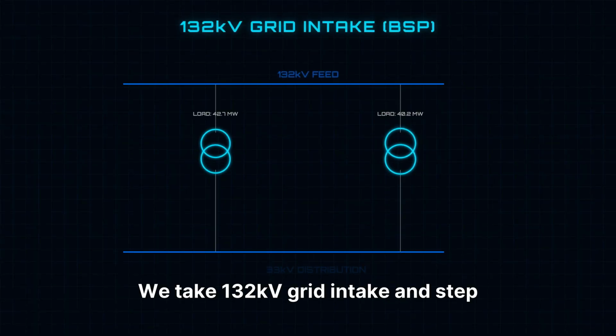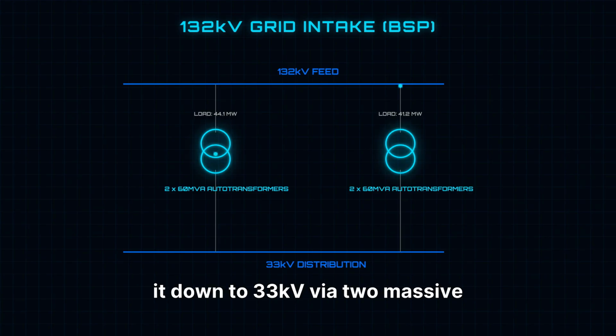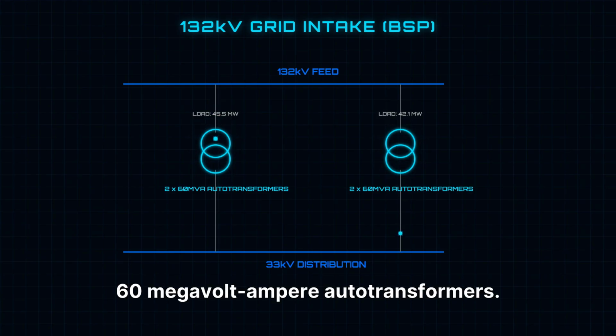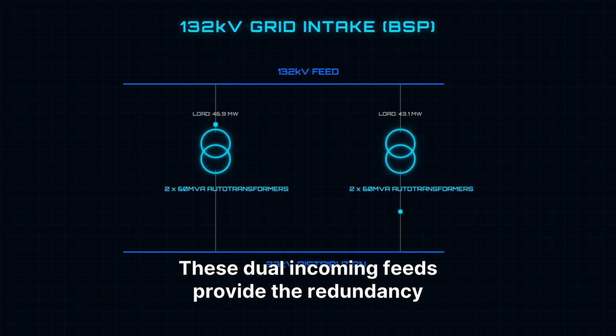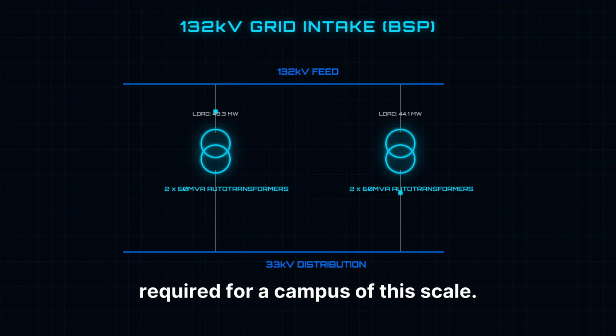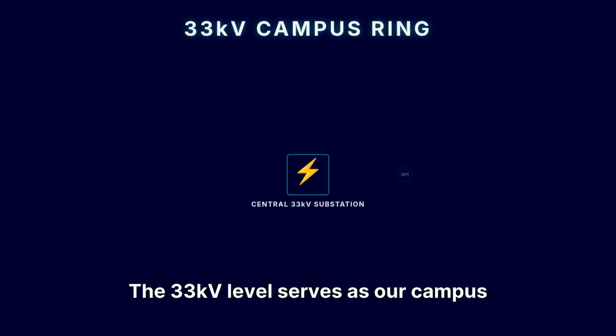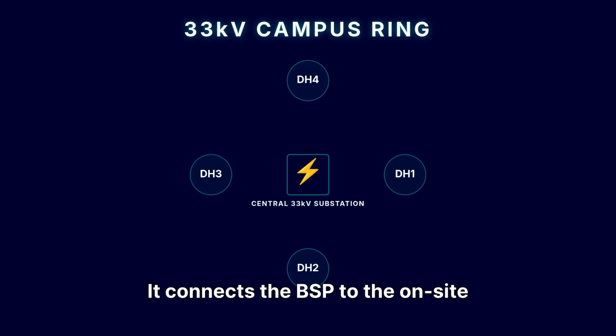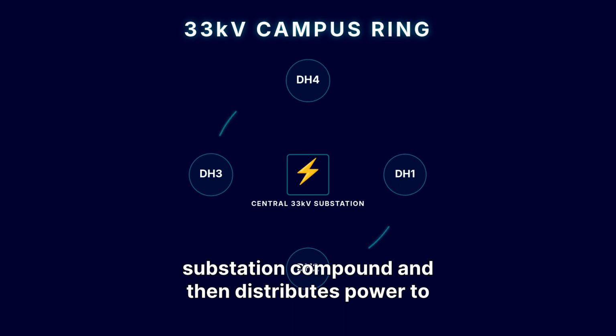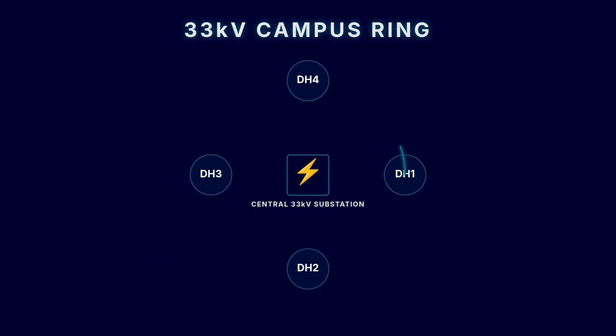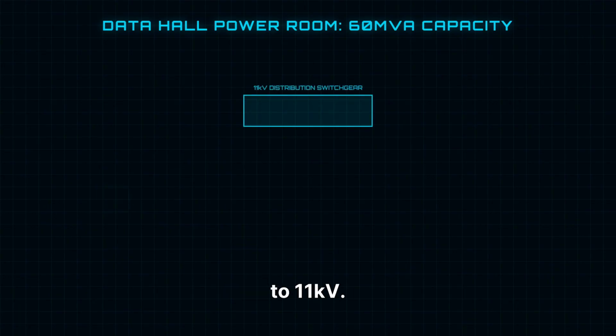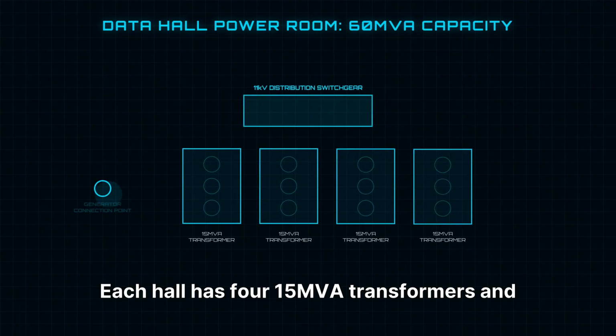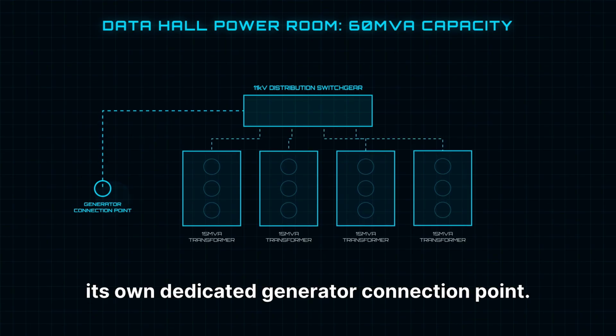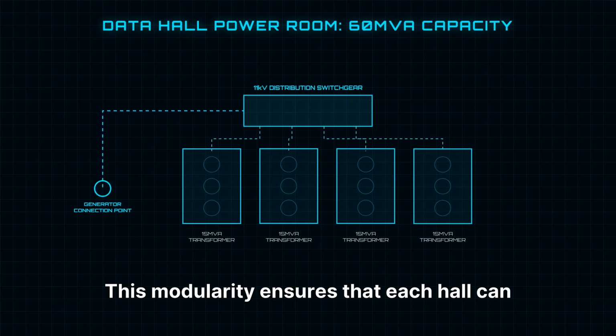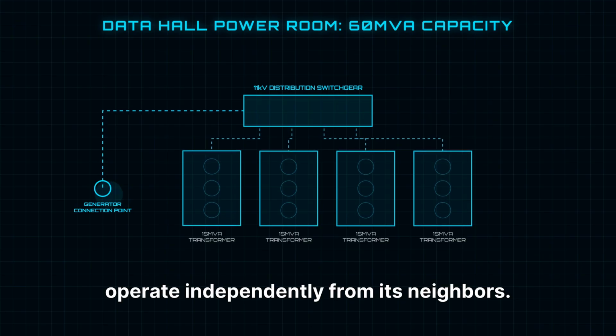We take 132 kV grid intake and step it down to 33 kV via two massive 60 megavolt ampere auto transformers. These dual incoming feeds provide the redundancy required for a campus of this scale. The 33 kV level serves as our campus distribution ring. It connects the BSP to the on-site substation compound and then distributes power to all four data halls simultaneously, ensuring balanced load sharing. At the hall level, we step down to 11 kV. Each hall has four 15 MVA transformers and its own dedicated generator connection point. This modularity ensures that each hall can operate independently from its neighbors.